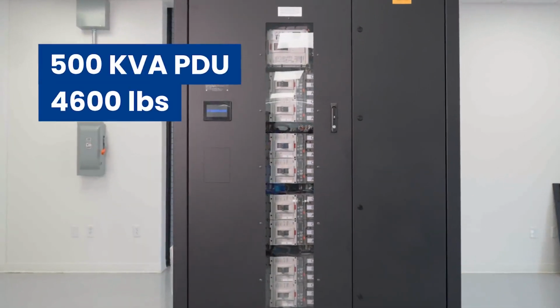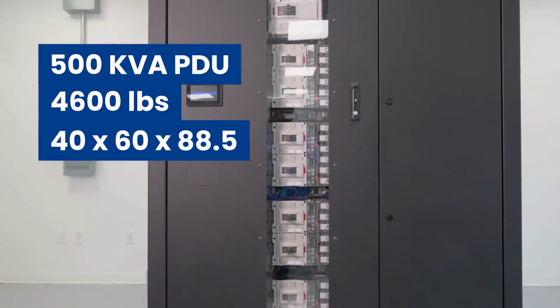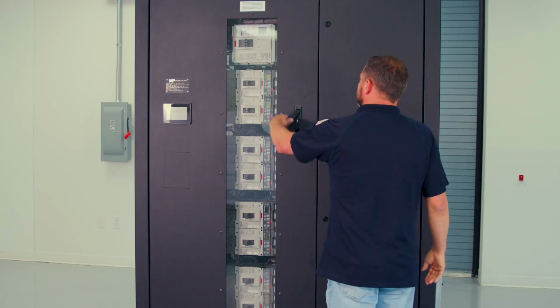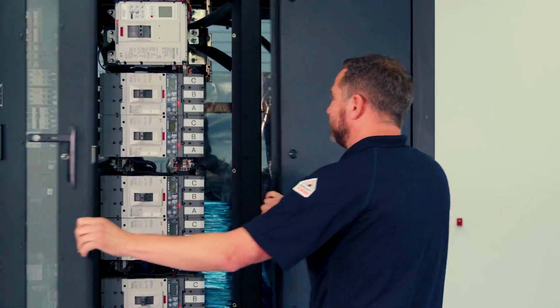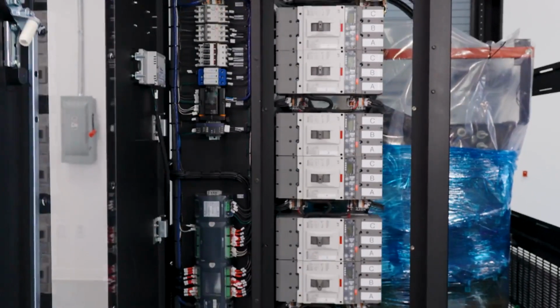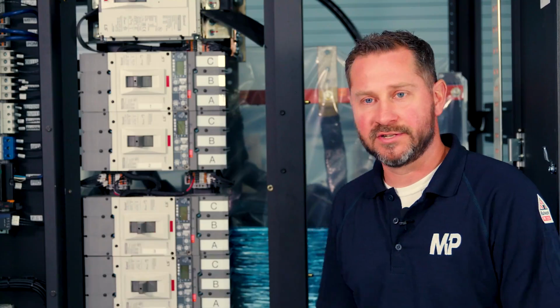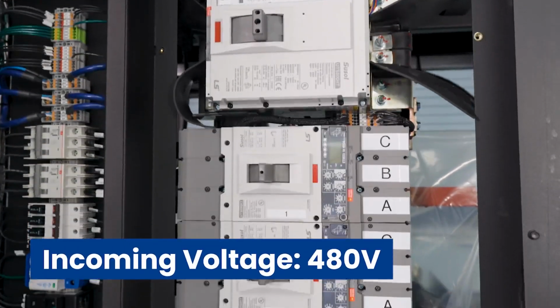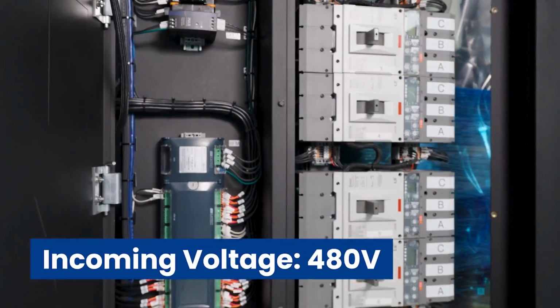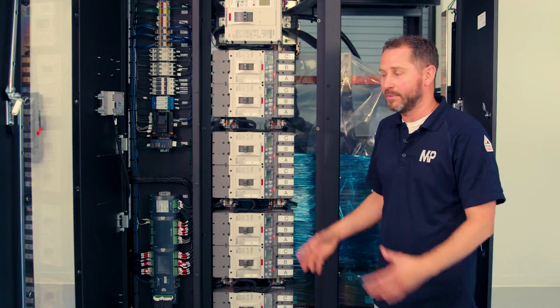This is a 500 kVA PDU, 4,600 pounds, 40 deep by 60 wide by 88.5 tall. Let's go ahead and open this up. The purpose of this PDU is to have our secondary voltage for a customer with incoming 480 volts. We can have different voltages coming off our secondary side safely and in a small footprint as well.